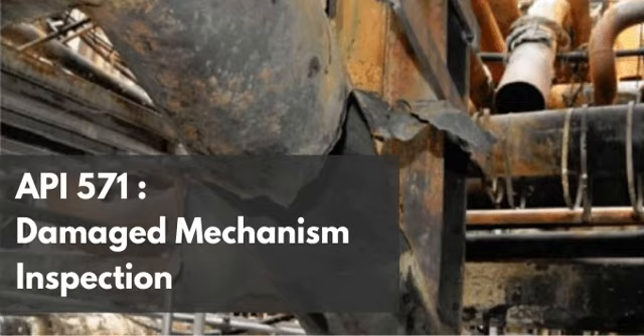Electromagnetic physics. How does an electromagnet find a microscopic crack? An ECT probe is physically pushed down the entire length of the tube. The probe generates an alternating magnetic field. When this magnetic field interacts with the conductive copper alloy wall, it induces small, circulating currents of electricity within the metal itself. These are the eddy currents. And those currents just flow smoothly as long as the metal is solid.